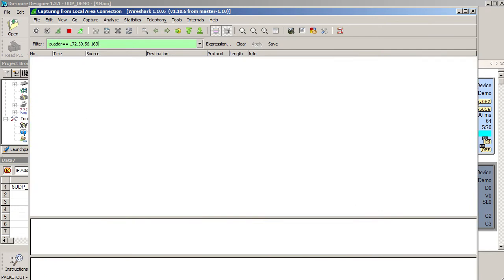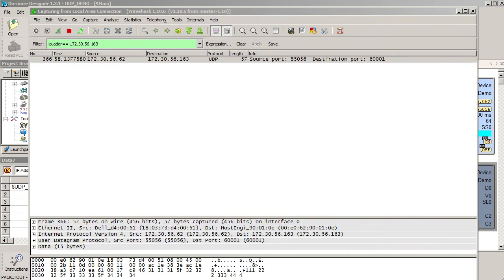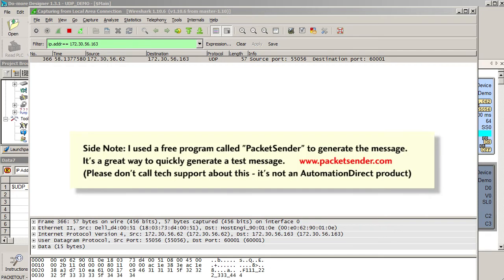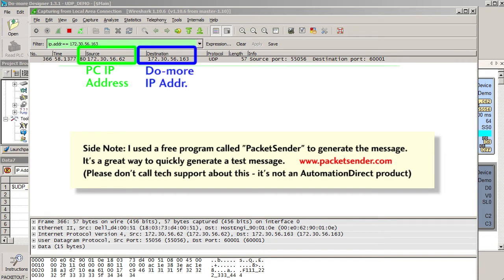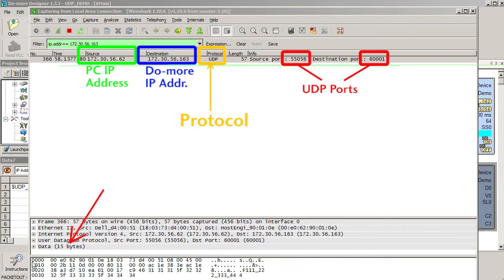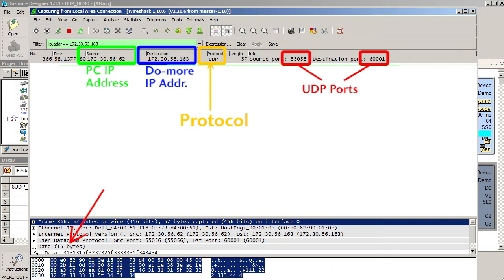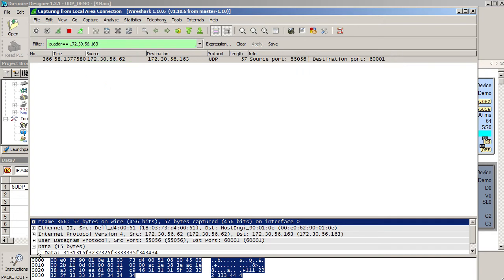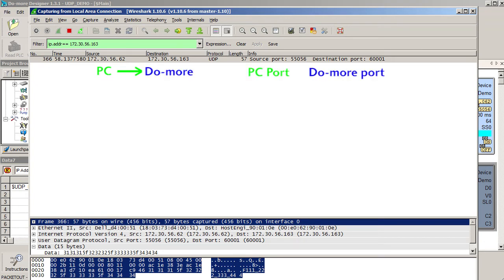Now I only see messages to or from the do-more. I'll send a message from the PC and sure enough I see that a message was sent from my PC's IP address to the do-more's IP address via UDP using these ports. And down here you can even see that 15 characters were sent and what they are in hex. So at a glance you can now tell that the message actually left this IP address, it went to this IP address and which UDP ports were used in the message.